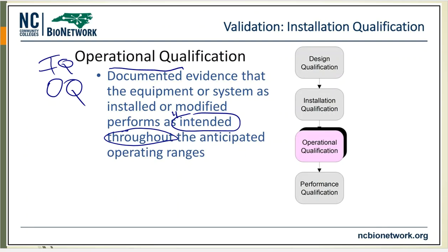All right, so in a laboratory setting, my machine would come in, they would install it, they would make sure it's working, it's all talking, it's communicating, and then if they're like, okay, well, what did you plan to do with this piece of instrumentation, Tracy? I'm going to go, well, these are the things that we're going to be doing with it, and then they're going to inject a sample, and that sample is going to be very similar to what I am trying to do with that machine, and they're going to go, okay, this is not exactly what you want, but it is similar to what you want, and this is proving to you that this machine can do that separation that you were after, or that analysis that you were after. That is what the operational qualification is all about.